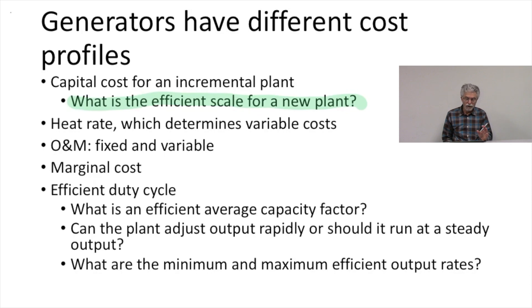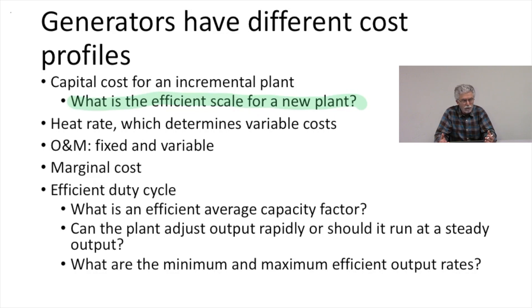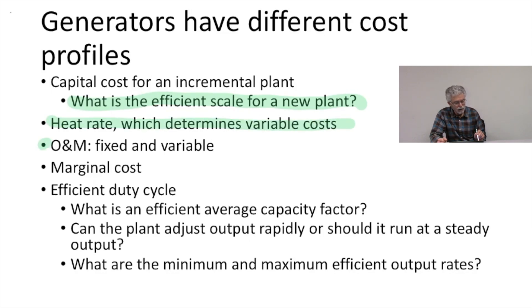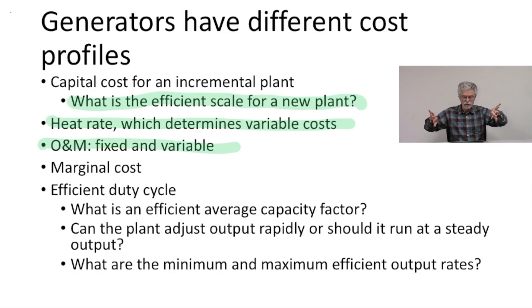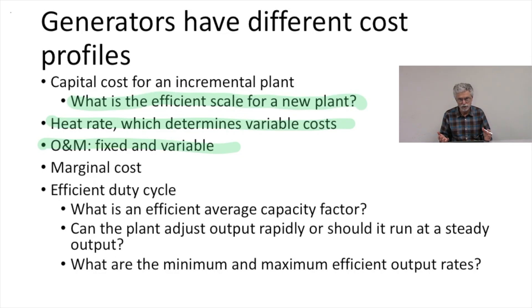A generating unit will have a heat rate — we talked about heat rates before. The heat rate is important because with fossil fuel fired power plants, the heat rate determines most of the variable cost of the power plant. So we'll be interested in the capital cost, the heat rate, and the operation and maintenance costs. We'll divide those up into fixed and variable costs, but any kind of new plant is going to have its own set of operation and maintenance costs as part of the plant's overall cost picture.